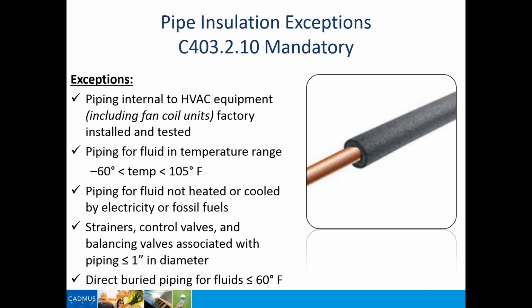The other exception is piping for fluid not heated or cooled by electricity or fossil fuels. So theoretically, hot water piping that is heated by solar would not be required to be insulated, because solar is not electricity or fossil fuels. So solar piping would actually be exempt, but depending on your hot water needs, you may want to go ahead and insulate those pipes anyway. Again, this is a minimum code requirement. It doesn't say that you shouldn't do that. It just says you're not required to, but good design practice might dictate that you do. So you have to look at what you're trying to accomplish for your design.